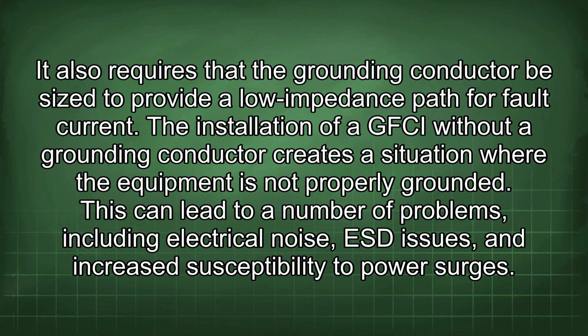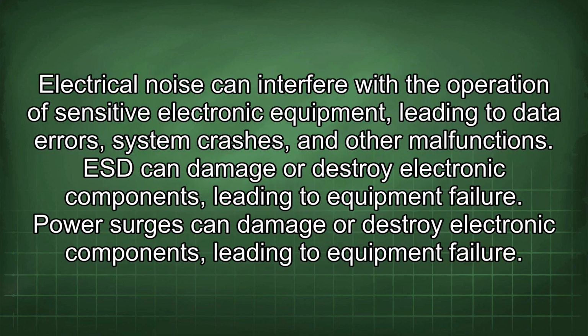The installation of a GFCI without a grounding conductor creates a situation where the equipment is not properly grounded. This can lead to a number of problems, including electrical noise, ESD issues, and increased susceptibility to power surges. Electrical noise can interfere with the operation of sensitive electronic equipment, leading to data errors, system crashes, and other malfunctions. ESD can damage or destroy electronic components, leading to equipment failure. Power surges can damage or destroy electronic components, leading to equipment failure.